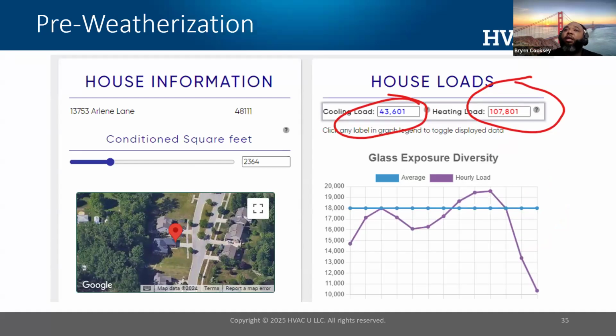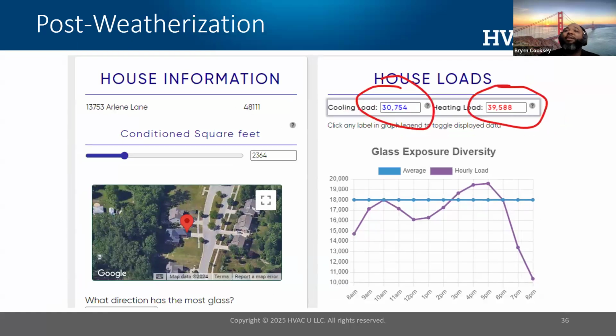This is a load report of a home, and in this home, I have a heating load of 107,000 BTUs. Okay, and I have a cooling load of 43,000 BTUs, so roughly a 3.5 ton air conditioner and a 107,000 furnace. This is pre-weatherization, so this was before I air seal and insulate. Let's look at what happens after I air seal and insulate just to the minimum code standard. Looking at my same house, I drop my heating load to 39,000 BTUs, and I reduce my system from a 3.5 ton system to a 2.5 ton system. So before using a heat pump to provide conditioning, you may have to weatherize your building shell. That's pretty important. If you don't, the load may be so large that your load may be bigger than what the biggest heat pump can deliver.